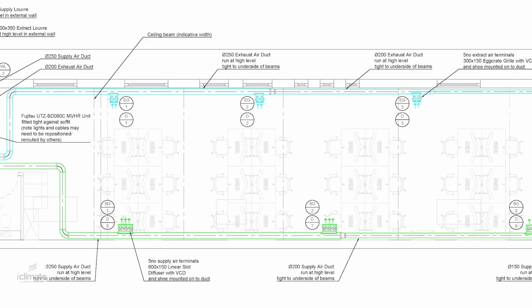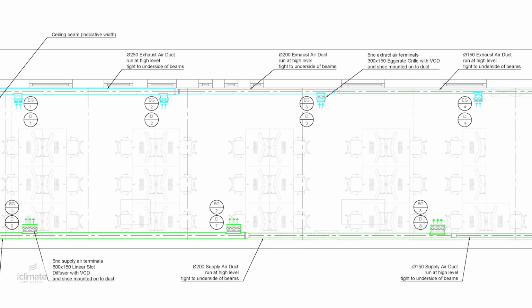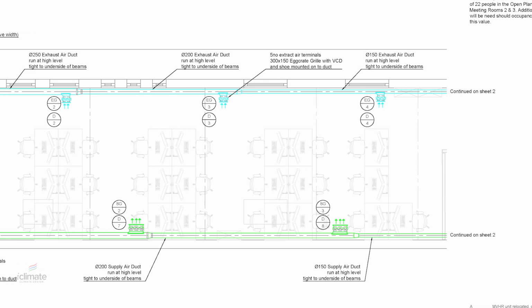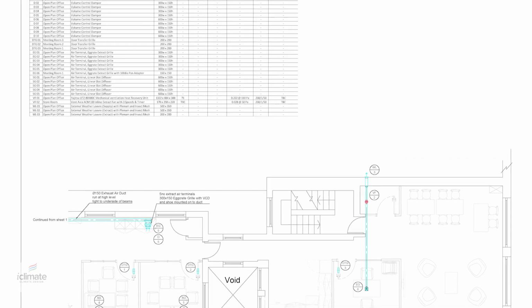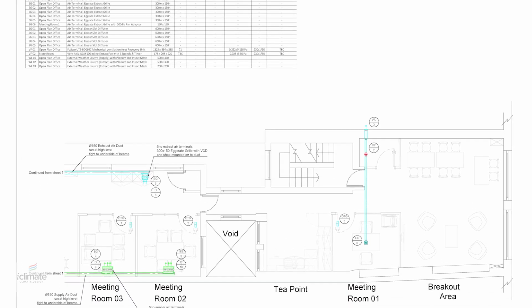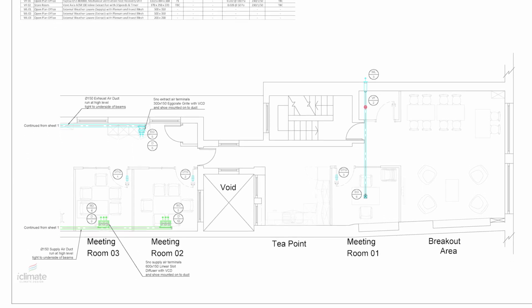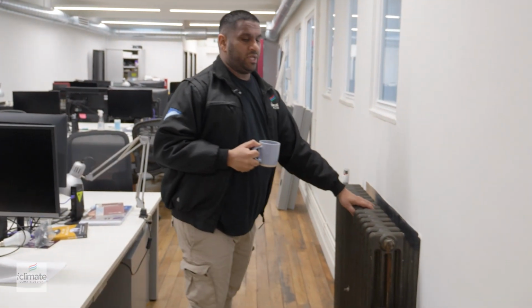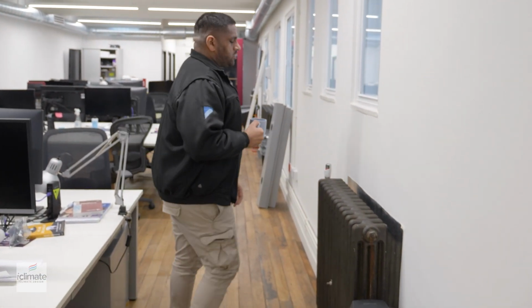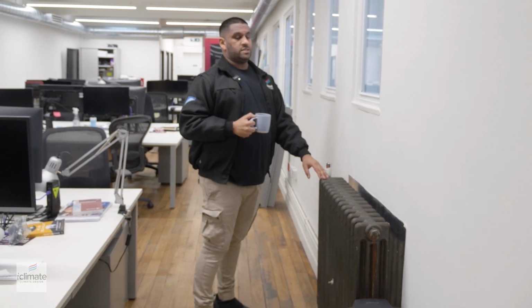And then the next step for the client is to work on an air source heat pump where they're going to remove the boiler for the radiators and we're going to switch to an air source heat pump. So it's better to take those calculations in a stage by stage process. Make sure you get your air changes right within the space and the fresh air per person for the occupancy, and then you work on the heat load and heat losses to bring comfort levels. These are the existing cast iron radiators fed by the boilers. So our next stage with the client is to replace these.